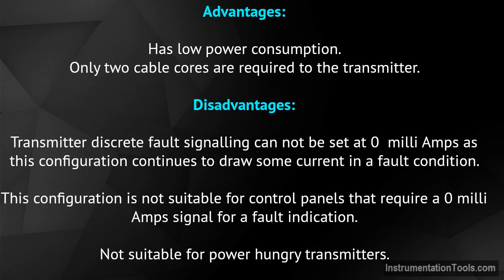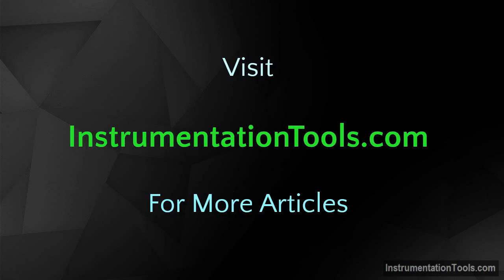Disadvantages: transmitter discrete fault signaling cannot be set at zero milliamps, as this configuration continues to draw some current in a fault condition. This configuration is not suitable for control panels that require a zero milliamp signal for a fault indication, and is not suitable for power-hungry transmitters. Visit instrumentationtools.com for more articles.